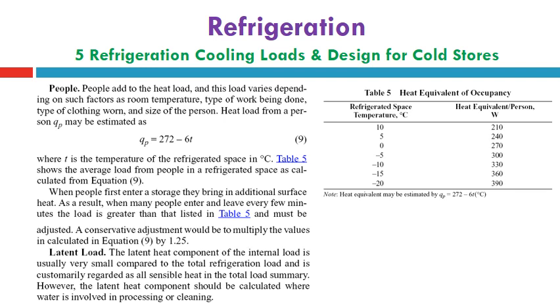We can find the people load. People add to the heat load, and this load varies depending on factors such as the room temperature, type of work being done, type of clothing worn, and the size of the person. Heat load from a person, Qp, may be estimated as Qp = 272 - 6t, where t is the temperature of the refrigerated space in degrees Celsius. Table 5, which is attached to this slide, shows the average load from people in refrigerated space as calculated from equation 9. These are the values of heat gain according to the refrigerated space temperature.